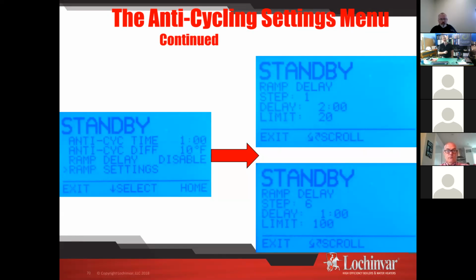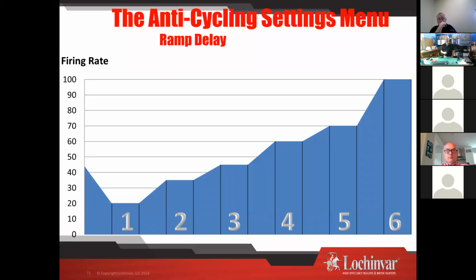And then just like we had in those night setbacks, we set stages. We have 6 stages for a delay and a limit. It ends up looking something like this. So now my boiler fires, my first stage there is 20%. Set it for a couple of minutes. Be as aggressive as you feel necessary. Look at your house design, your system. If I have hydroair, I might be a little less aggressive on the front end just because I want to get a little heat out there. I don't want to blow some cold air and that sort of stuff. They'll get frustrated. If I have baseboard, if I have radiant, if I have snow melt, any of that sort of stuff, be aggressive in slowing that boiler down.